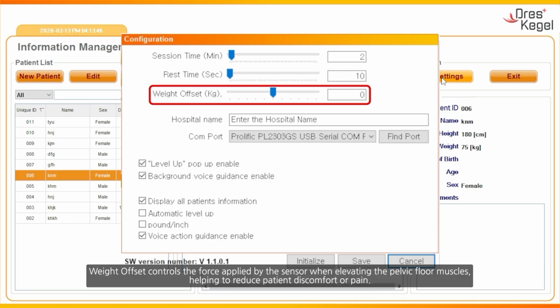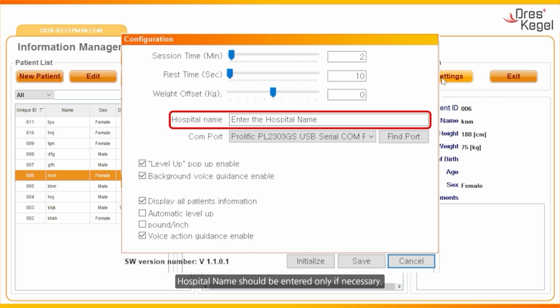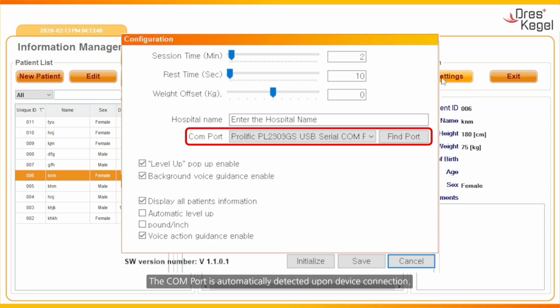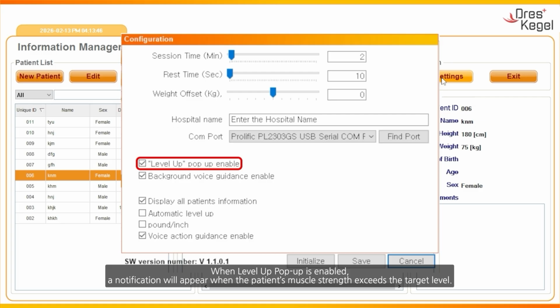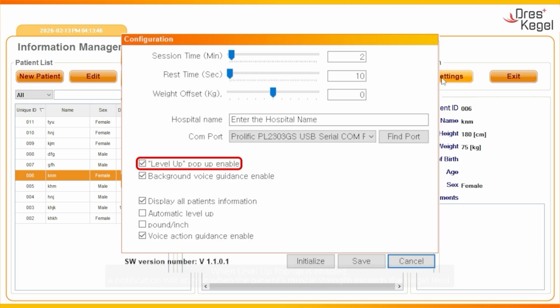Weight offset controls the force applied by the sensor when elevating the pelvic floor muscles, helping to reduce patient discomfort or pain. Hospital name should be entered only if necessary. The COM port is automatically detected upon device connection. When Level Up pop-up is enabled, a notification will appear when the patient's muscle strength exceeds the target level.